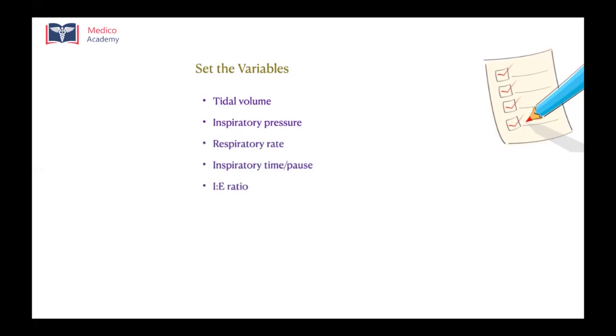The next would be respiratory rate, the inspiratory time as well as the inspiratory pause, depending on the ventilator and the mode selected. There'll be an IE ratio which you may have to set, that is the ratio between inspiratory time and expiratory time. There'll be an inspiratory flow which you will need to select. PEEP and FiO2. PEEP, we have already discussed, is positive end expiratory pressure, and FiO2 is fraction of inspired oxygen, and inspiratory trigger. So these are the various variables that we need to set. Now let's go into the details of each variable, how and what to do about these variables.